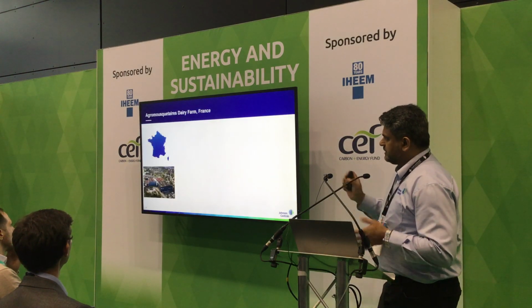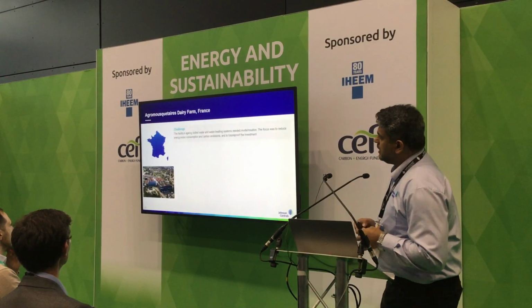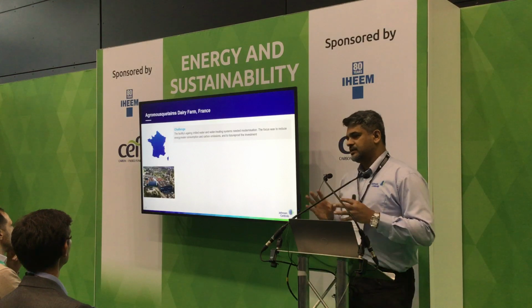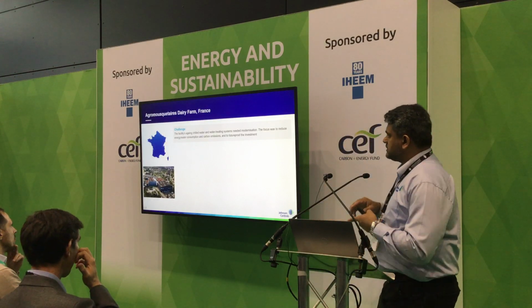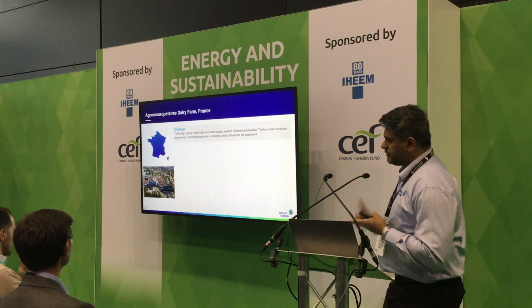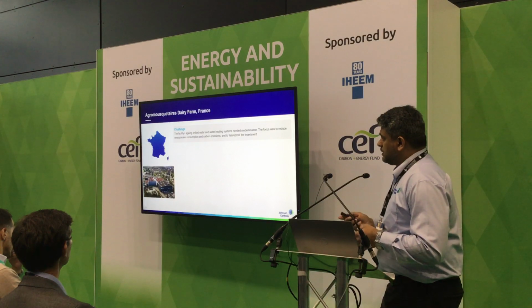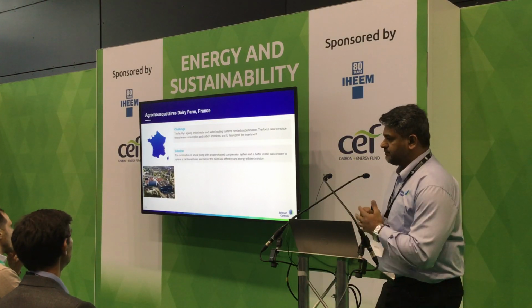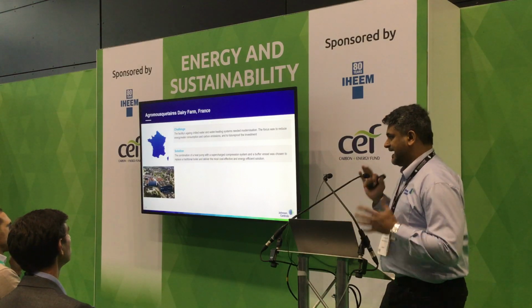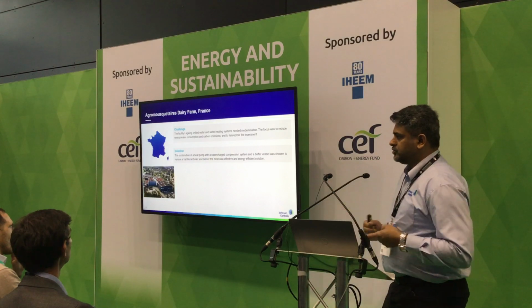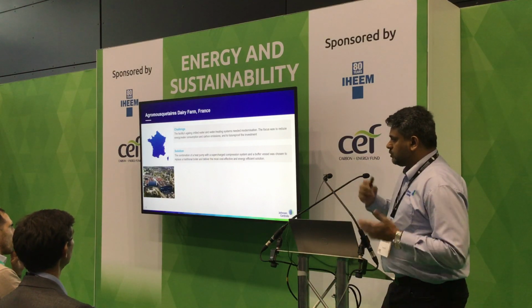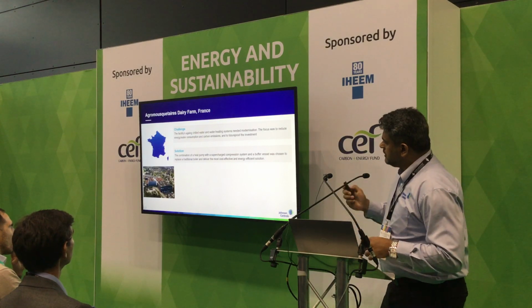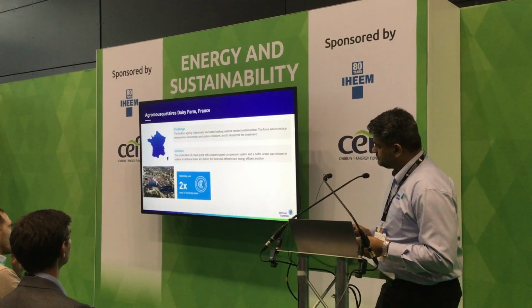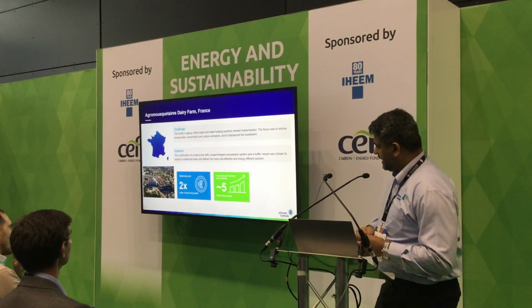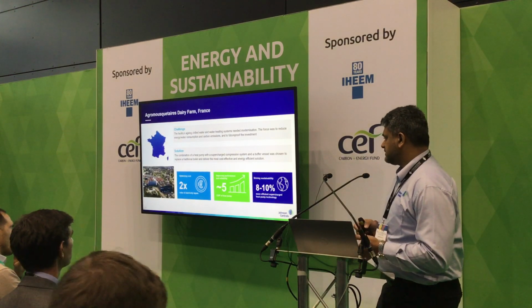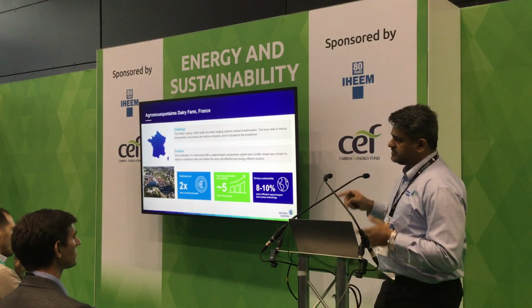Another example, not exactly healthcare, but showcasing some technology. Agromousquetaires dairy farm. They had an aging facility which they wanted to refab, but their focus was to reduce energy and water consumption and also reduce carbon emissions, and they wanted to future-proof it. What we did was a combination of a heat pump with a supercharged compression system and a buffer vessel. This is an engineered solution specific to that site, using natural refrigerant because they wanted to future-proof. They didn't want to have those environmental impacts in the future. So we were able to double their savings, with a COP of more than 5 for that heat pump, and it resulted in about 10% more efficient operation because of that specific technology being used.